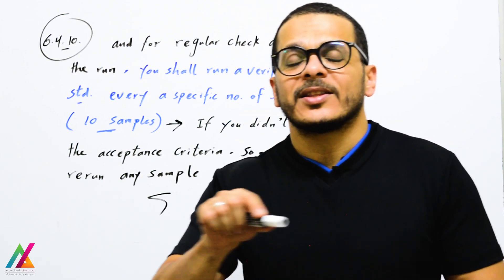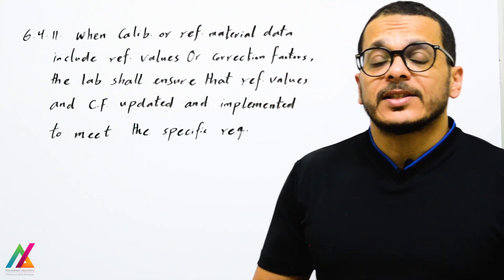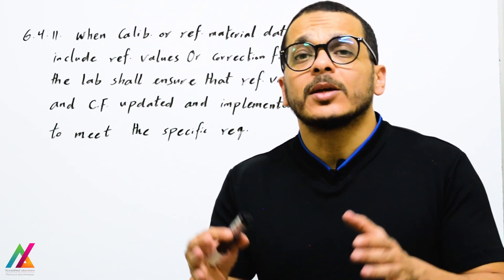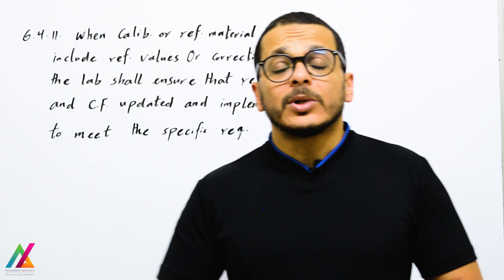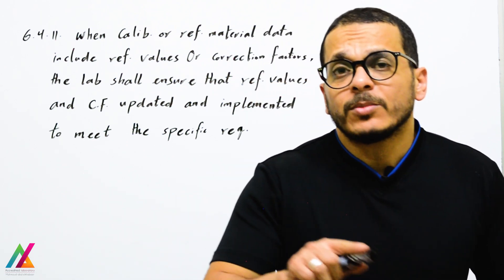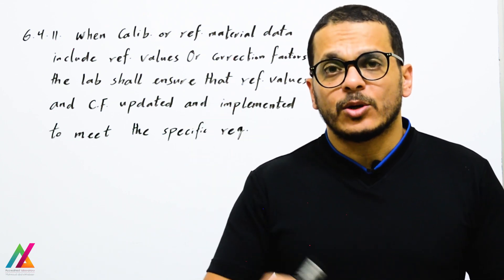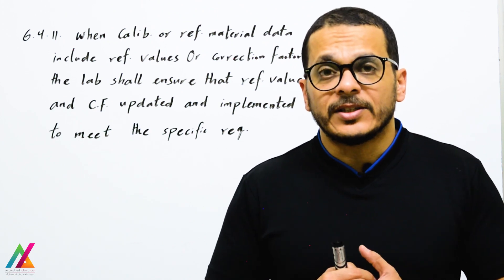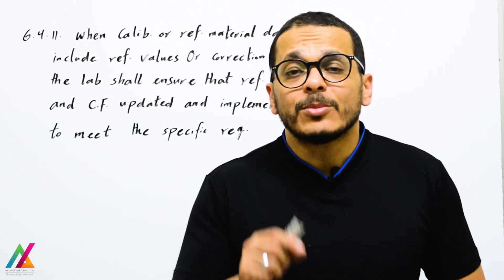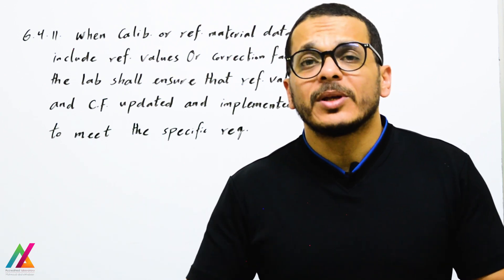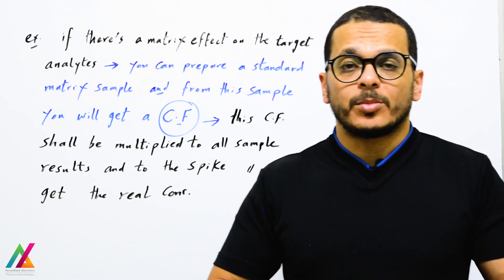When calibration or reference material data include reference values or correction factors, the lab shall ensure these are updated and implemented to meet specified requirements. This point may not apply to all labs, but if you have correction factors to multiply to the final result to get the real concentration, these should ideally be entered into the instrument sequence, or applied in software outside the instrument — but applying them within the instrument itself is preferred to ensure they are consistently applied.